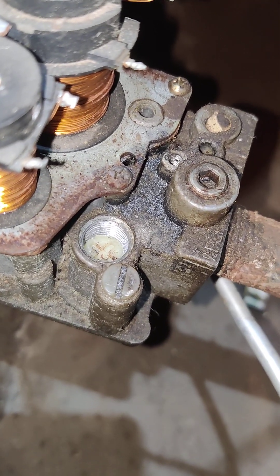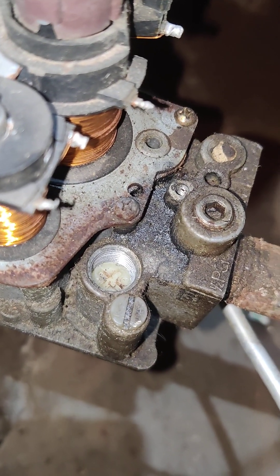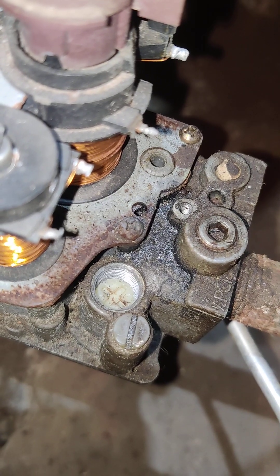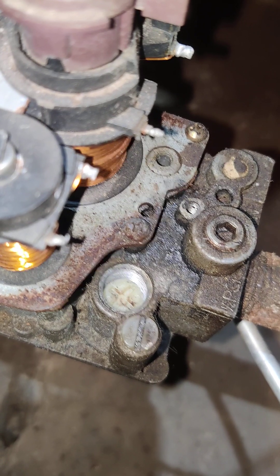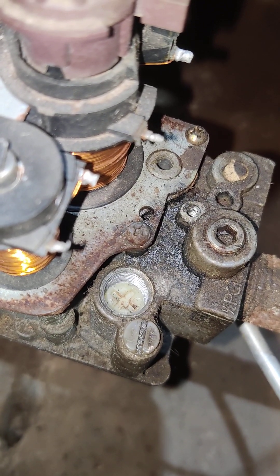Or they make a special T-handle or a cross-shaped spanner for it. And I'll show you the issue I was having. Clockwise turning it right increases pressure. It's a spring valve, so you're basically opening the opening more when you screw it in, reducing the opening size when you turn it left and unscrew it.